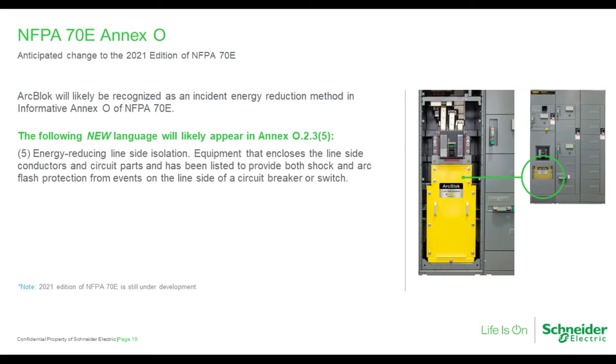Now, Annex O deals with safety-related design concepts, things that facility owners, facility managers, and employers should consider when designing an electrical installation. The new language will add energy-reducing line-side isolation to the list of incident energy reduction methods. It will describe equipment that encloses the line-side conductors and circuit parts and has been evaluated to provide both shock and arc flash protection from events on the line side of a circuit breaker or switch. So now I'll turn it over to Tim Faber, who can explain more about this type of approach.